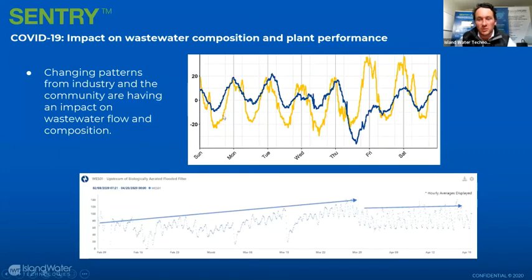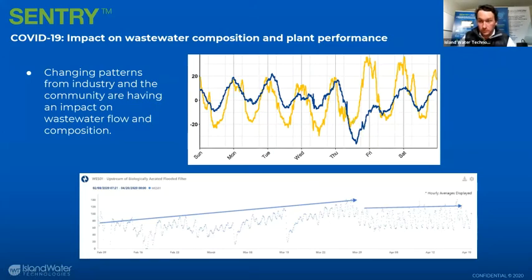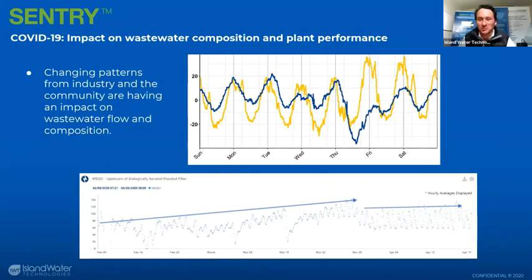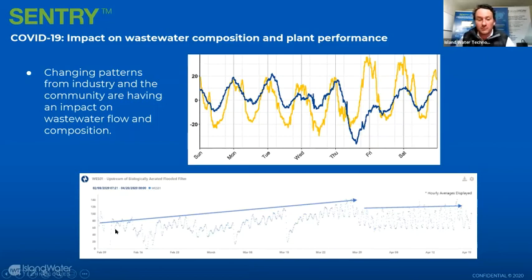The blue line shows the traditional weekly pattern from January — not necessarily as uniform. Then post-COVID, things have become more regular, certainly on the weekends as well. What it shows is that what was happening at the weekend is now mimicking itself during the week, which it wasn't previously. Things are more routine. The aggregate overlay shows this, and being able to see that progression — whether the weekly pattern is shifting, whether the organic load looks like it's coming up or flattening — and how that changes over time is also super interesting.